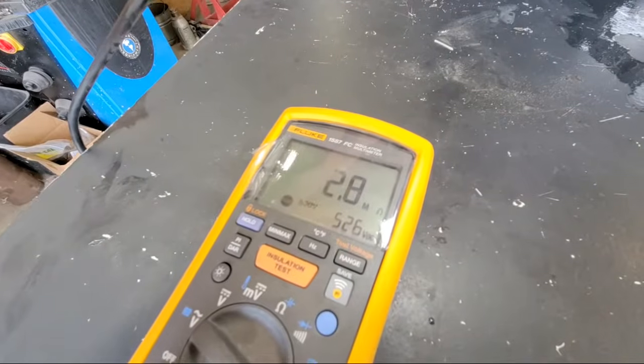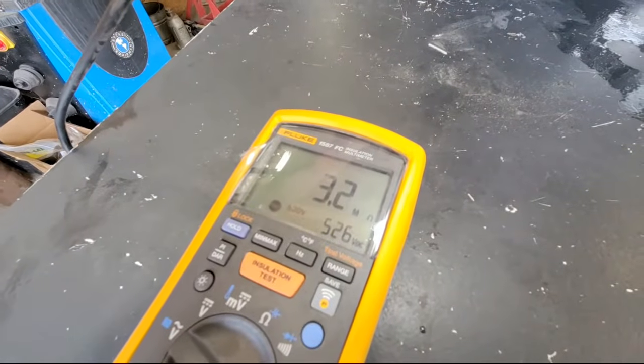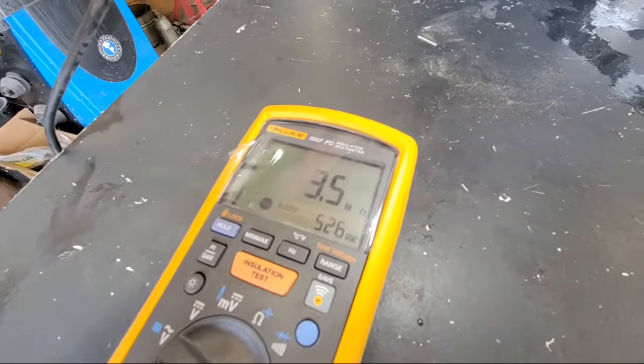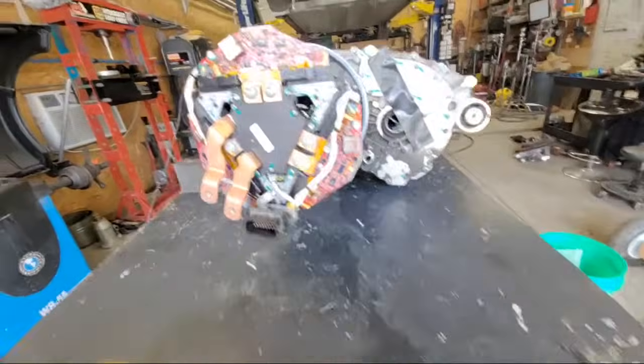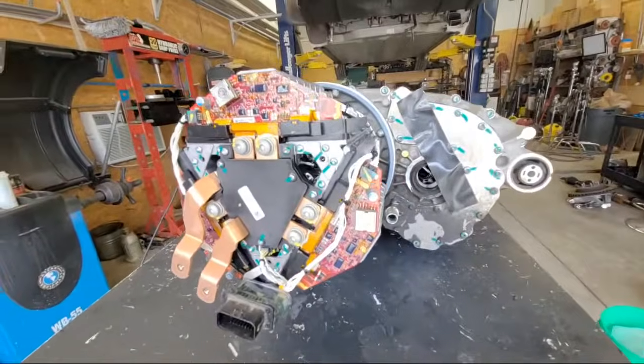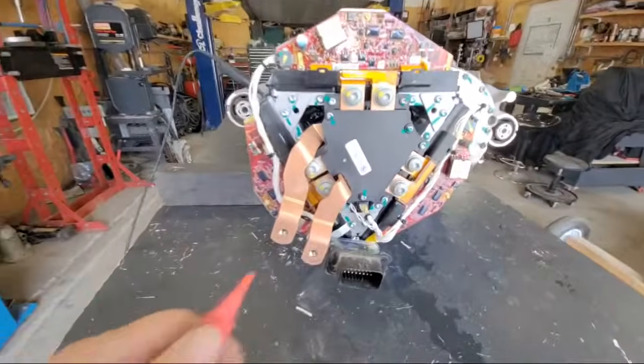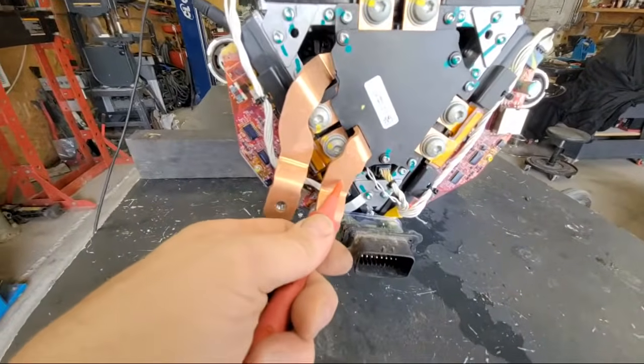Okay, so it's still there, 1.9, and it starts going up to 3.2 million. That tells me there's still some moisture in there because it's leaking the voltage, the voltage is decaying. Let's check the negative side.